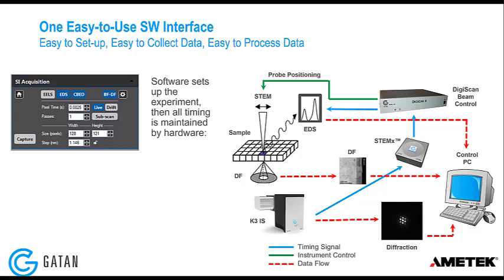The camera is the timing master, and we use hardware synchronization, so we collect 4D STEM data sets at the speed at which the camera is operated. With OneView you can go from 25 to 300 frames per second depending on binning. With K3IS you can go from 150 frames per second up to more than 3,500 frames per second by reading out smaller sub-areas of the sensor.